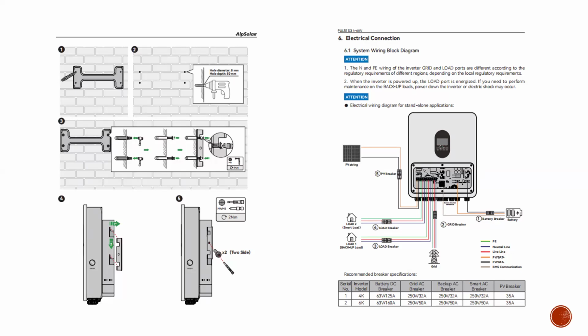And also where I do have a problem is the PV. The PV breaker should not exceed 35 amps because the maximum short circuit current for this unit is 35 amps. And there's a high voltage inbuilt MPPT, which allows you to connect your panels in series. And when you are building in series, it means you are not building current. So a 35 amps DC breaker should be enough.